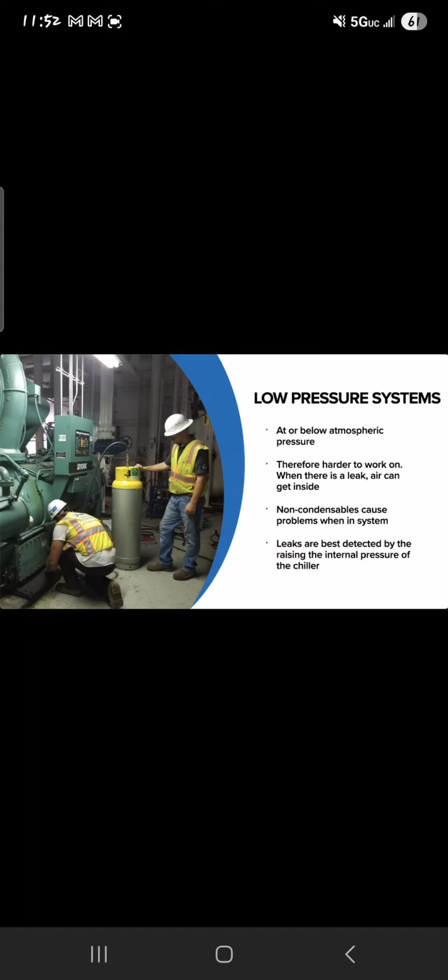All right. Another thing I'll tell you, low pressure systems have what is known as a rupture disc. Remember, they operate at low pressure. So if for any reason they start to build pressure, that pressure has got to be ejected. All right. So a rupture disc is a sacrificial disc that if you build up internal pressure, it's going to rupture that disc. That needs to be piped to the outside. Anything that relieves pressure, pressure relief, rupture disc, you can't vent them inside. They got to be vented outside. Okay. And you will more than likely see questions on that.